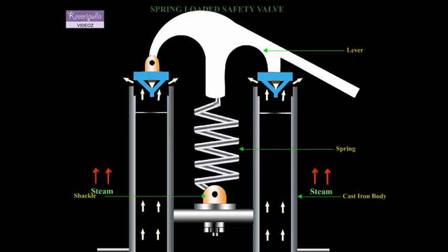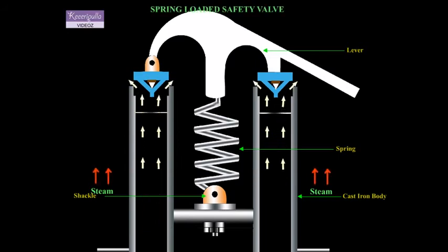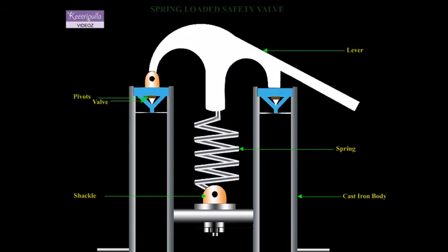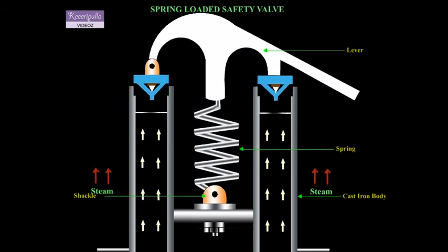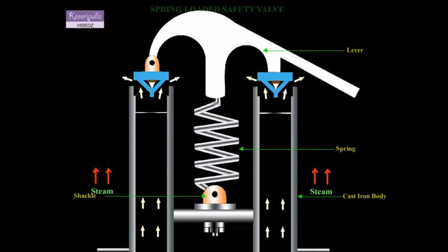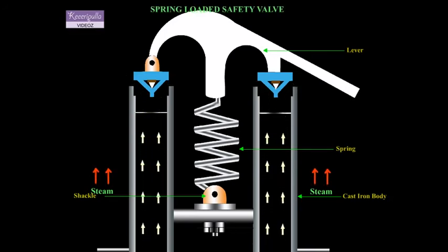The spring-loaded safety valve is actuated when the steam pressure exceeds the safe working pressure. The valves rise up against the action of the spring due to the excess pressure of the steam inside the boiler, and allow the steam to escape from inside the boiler, till the pressure in the boiler drops to the safe working pressure.